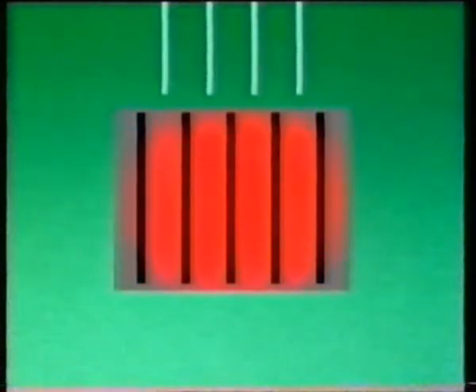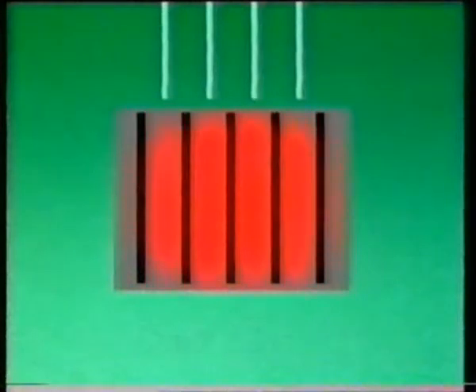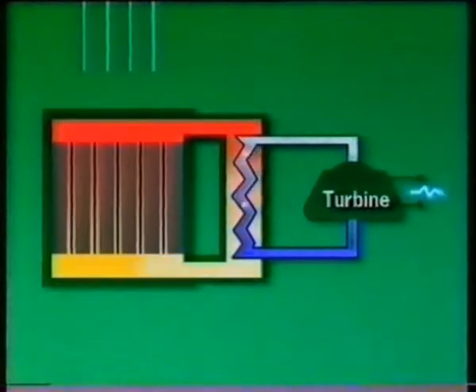Given a critical amount of fuel and a moderator, the chain reaction would proceed, but uncontrolled. So a third basic part of a reactor is a control system to stop and start a reaction as necessary, to control the energy being released. There are some materials which soak up neutrons — they absorb them like sponges absorb water. If rods of neutron absorber are placed in our reactor, they stop the reaction. Our reactor is now working, can be turned on and off, and is capable of producing great heat. This heat has to be carried away out of the reactor so water can be boiled to make steam. So a coolant is pumped around the reactor; it carries away the heat to heat exchangers where it gives its heat to water which boils to make steam, to drive the turbines, and so on. This, then, is the basic nuclear reactor: fuel, moderator, control system, coolant.